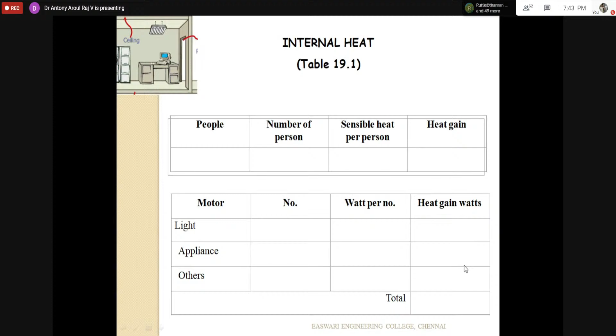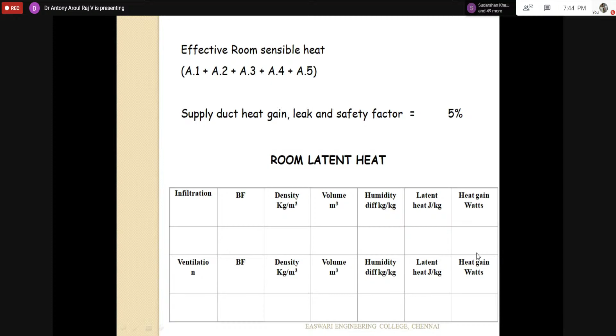Then we are going for room latent heat, because of outdoor air — because of infiltration, ventilation, the bypass factor, all this component. Here you can see this is humidity difference, not temperature difference. Humidity difference multiplied by latent heat gives the heat gain, the room latent heat gain because of outdoor air. So that also we are calculating.